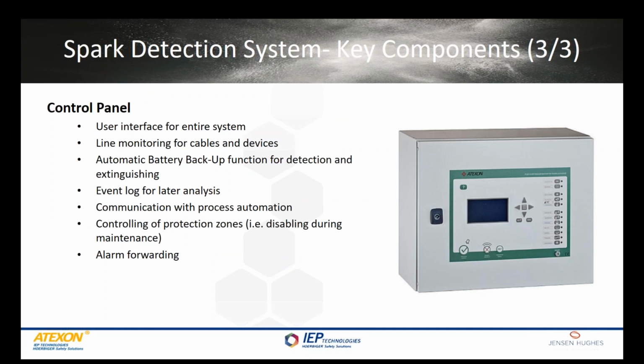Third key component is the control panel, which is the user interface for the entire system. It has line monitoring for cables and devices. There is an automatic battery backup function for detection and extinguishing. There is an event log for later analysis that contains, for example, alarms, failures, performed tests, etc.